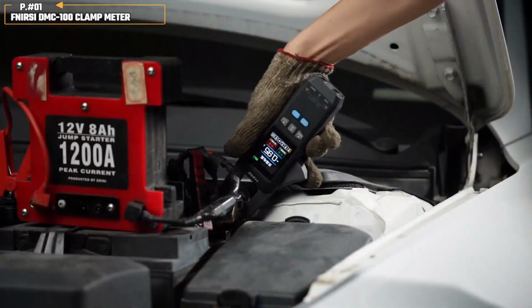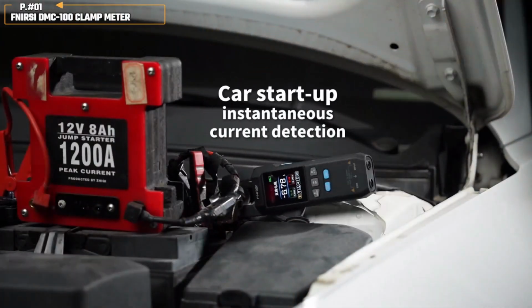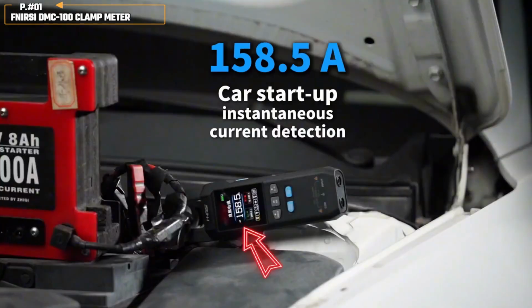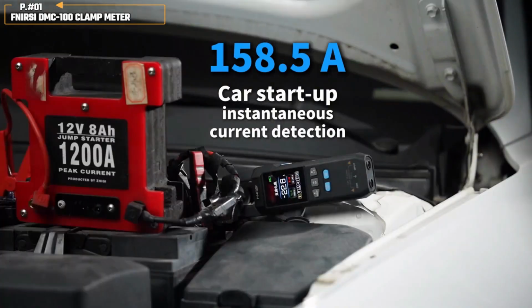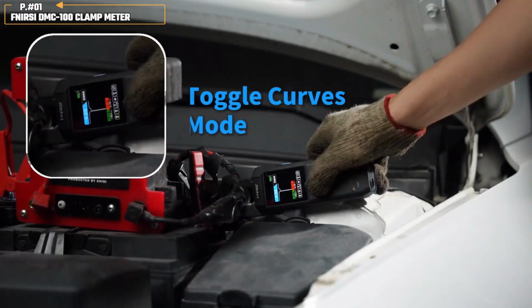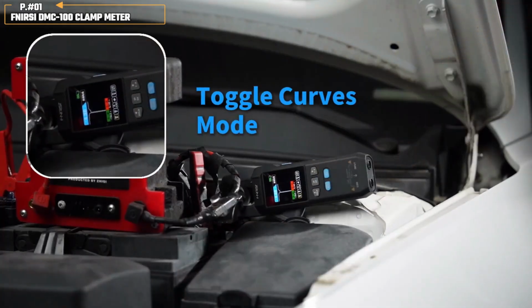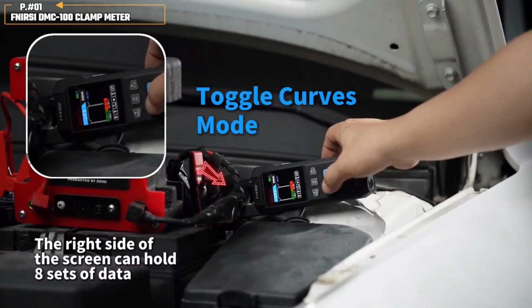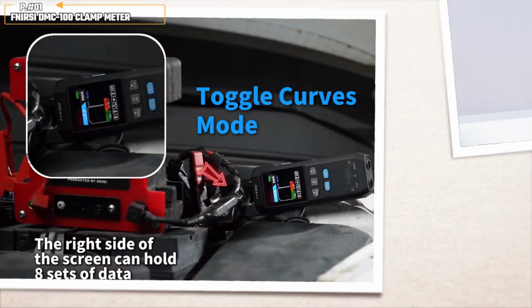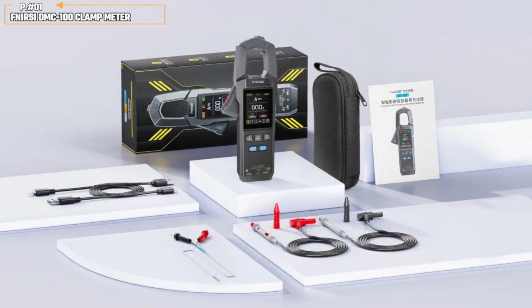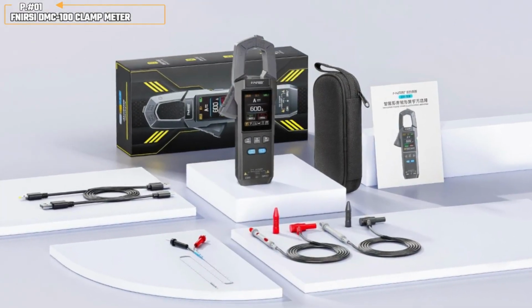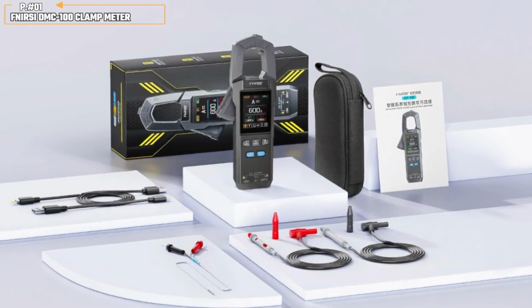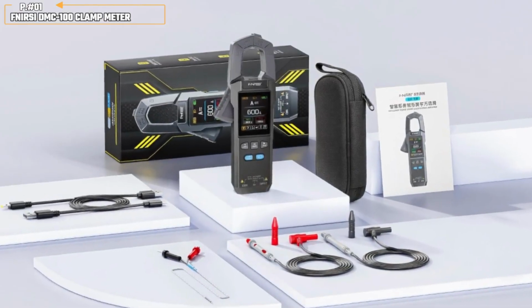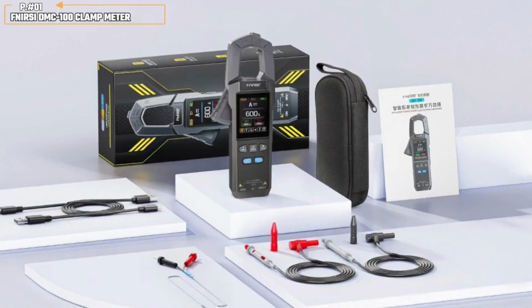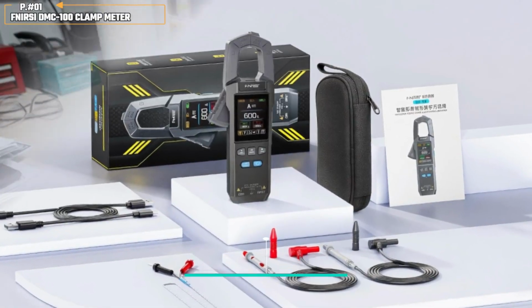Independent testing found strong voltage and resistance results. However, clamp current readings can shift slightly with the meter's position. For better DC results, zero the meter first and keep the conductor centered inside the jaw. The graph is useful for tracking trends, but it is not an oscilloscope. Its 0.01 amp low-range resolution is also too coarse for very small milliamp battery drains, and the built-in battery must be recharged rather than quickly replaced.